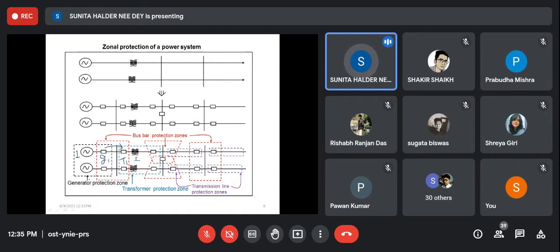So this is the generator protection zone. The dotted line shows the bus bar protection. This protection of transformer 1 is also protecting the bus bar. You can see there is overlapping, the black dotted line and the red dotted line. That means there is always some overlapping between the protection zones. In other words, there is some backup protection along with primary protection, so that we can give complete protection to the system. If there is a fault, it should be disconnected, maybe instantaneously, maybe after some time lag. Why time lag? Say when there is a fault in generator 1, we should expect that G1 will operate first.